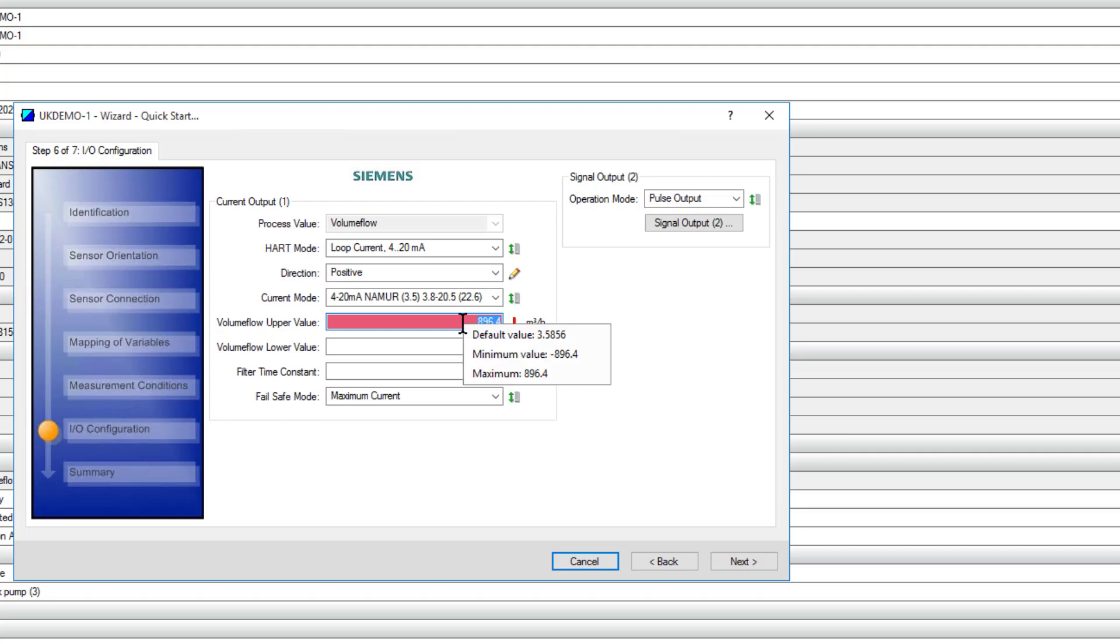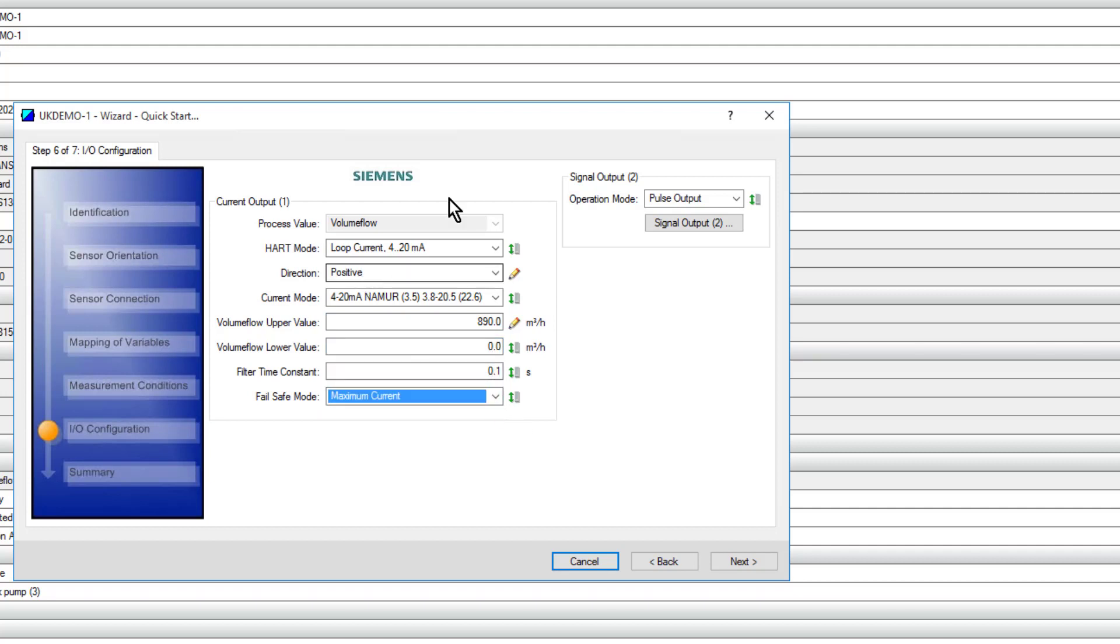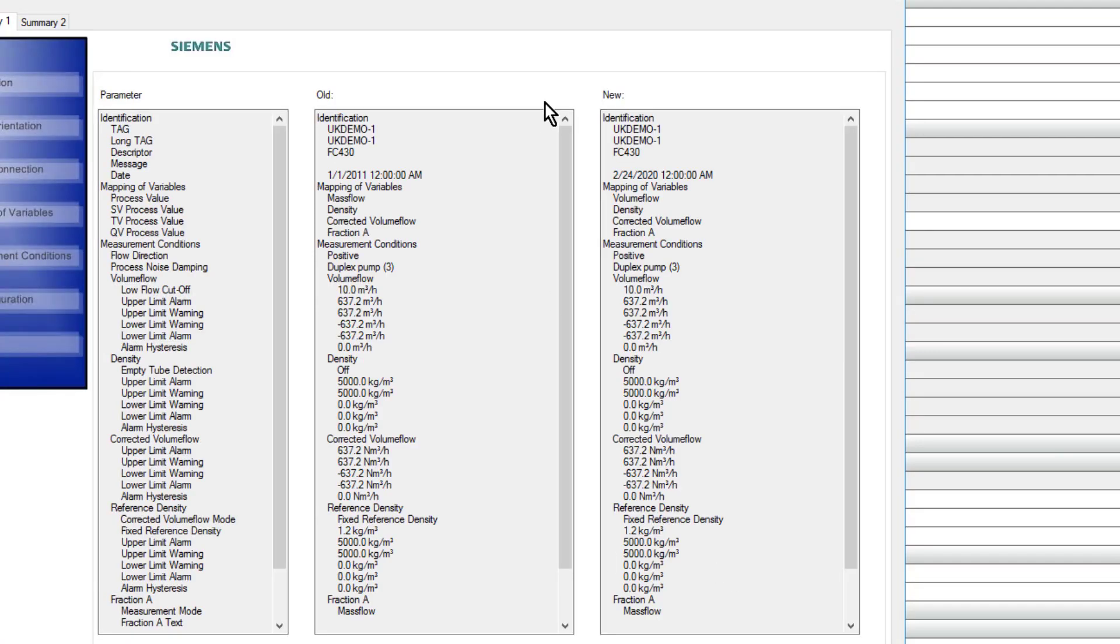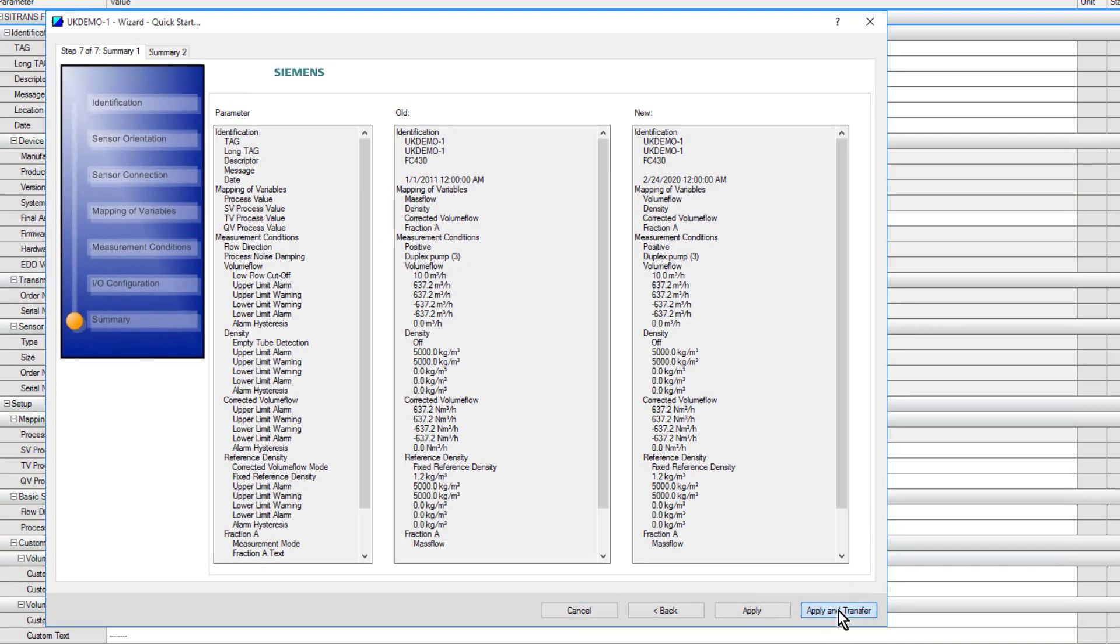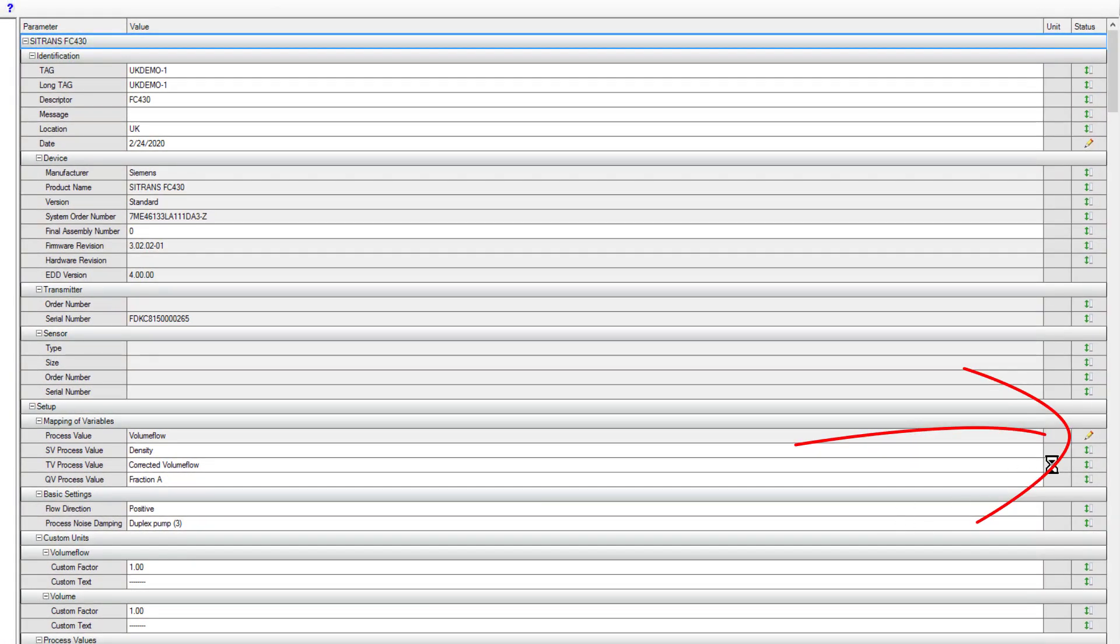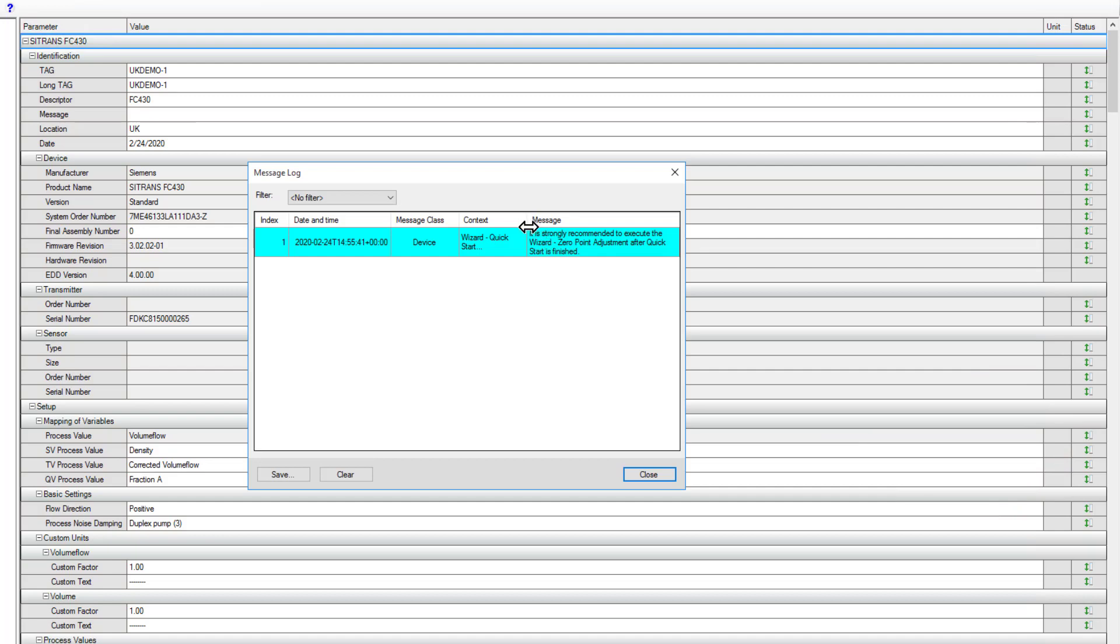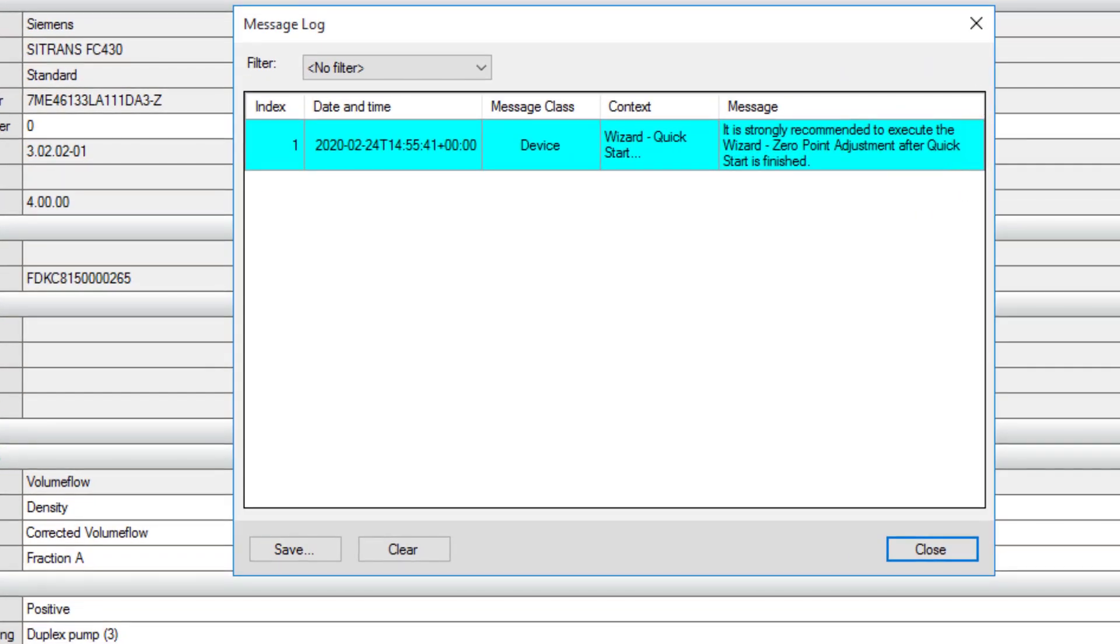Then you have to set the flow rate. If you right-click the box, you can see the options. We're going to put in here 890. Low flow value, time constant, and then your fail-safe settings. There is my milliamp range. I get old and new, and then I just click on apply and transfer. That's going to apply the parameters to this table. You can see here one that has changed—it's gone to a pencil. Then it's going to download it to the device.